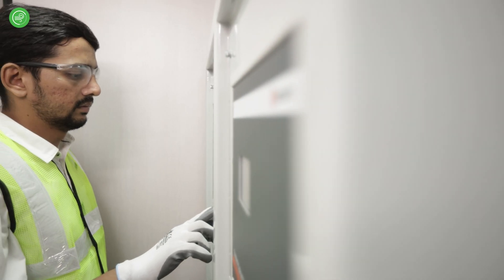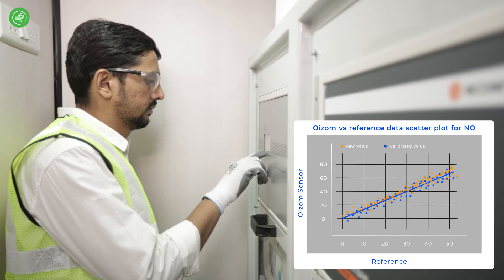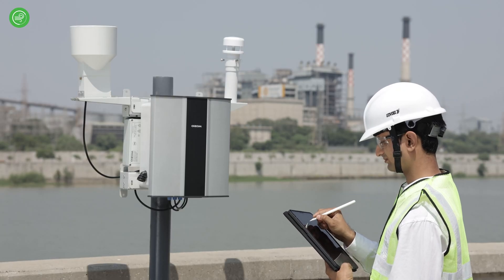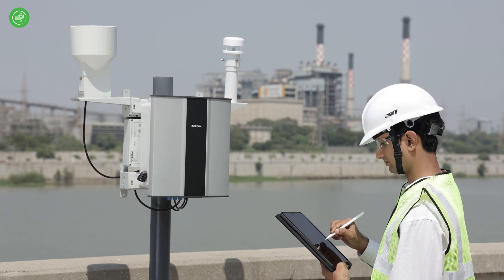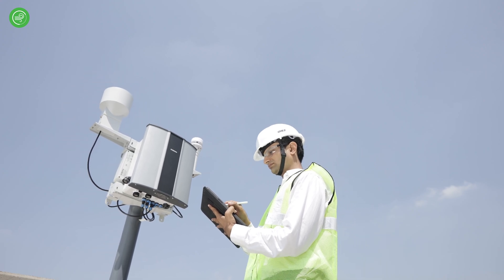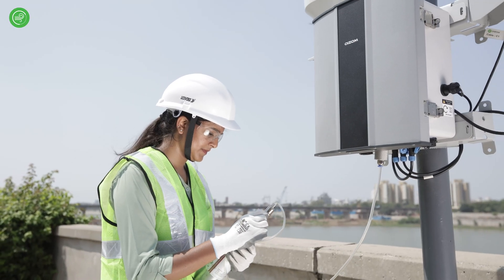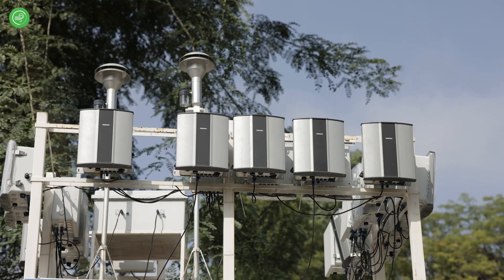If users have access to a reference station, Oizom monitors can be calibrated to match the monitoring site's geographic, topographic, and climatic conditions. However, if a reference station is not available, Oizom devices have built-in advanced algorithms that can apply baseline corrections based on local climatic conditions. Additionally, the device can be spot calibrated using standard calibration gas cylinders of known concentrations or by being co-located with a reference standard.